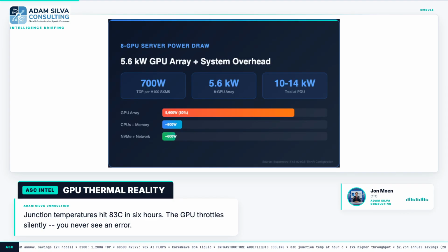What happens when air-cooled H100s hit hour 6? The H100 SXM5 has a 700-watt TDP. In an 8 GPU configuration, that is 5.6 kilowatts from the GPU array alone. A fully loaded training server draws between 10 and 14 kilowatts at the PDU. Air cooling moves that heat through high static pressure fans and rear exhaust airflow. Under burst workloads, this works.